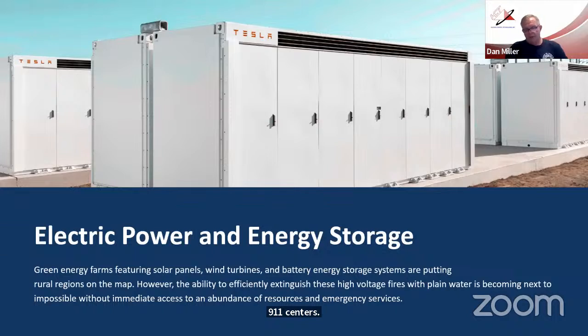So an uninterruptible power supply may no longer have lead acid batteries in it—it may have lithium-ion batteries instead. That's another fire hazard, because the outcomes with lithium-ion batteries are different than with lead acid batteries when you have a fire, whether internally generated within the BESS unit or from an external fire exposing it. Either way, you get a much more intense and hazardous outcome because of the presence of the lithium-ion batteries.